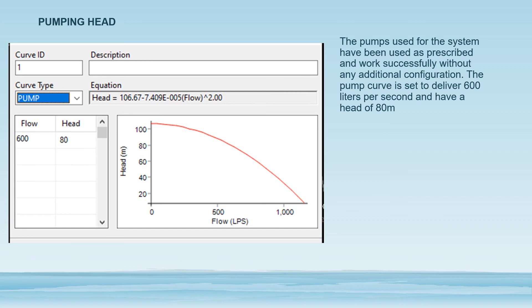We have pumping head. The pumps used in the system have been used as prescribed and work successfully without any additional configuration. The pump curve is set to deliver 600 liters per second and have a head of 80 meters. As you can see here, as shown on the EPANET software, the pump curve ID is set to one, the curve type is pump, the flow is 600 liters per second, and the head is 80 meters. This is the graph representing the relationship between the head and the flow.